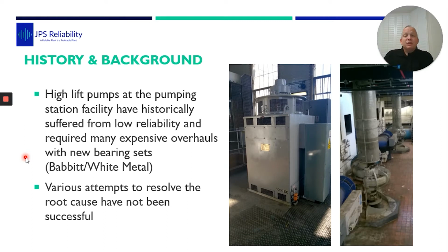Everyone, the fitters, the mechanics, electricians, process, all had their own opinions of what was causing the failure, which added more confusion. Previous experts have been in doing non-standard tests, like in the MCCs, and calling misalignment as the issue when they're not actually looking at the system and could see it's a cardan shaft. So various attempts have been made to resolve it.